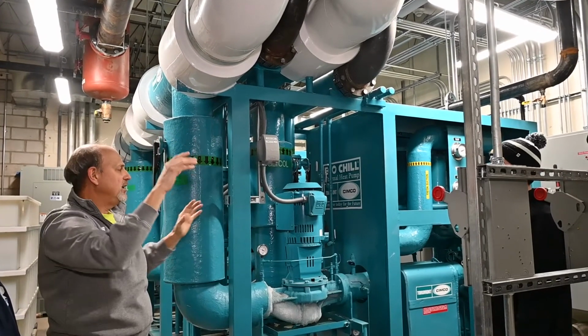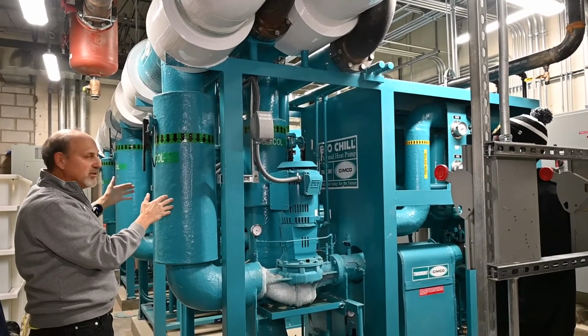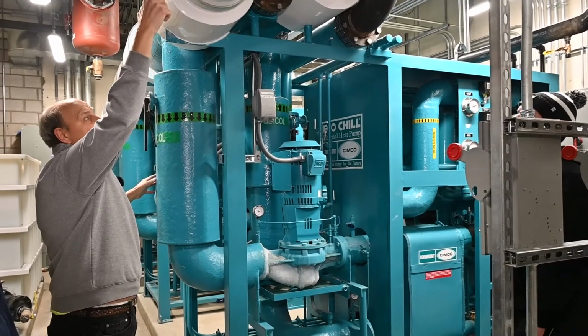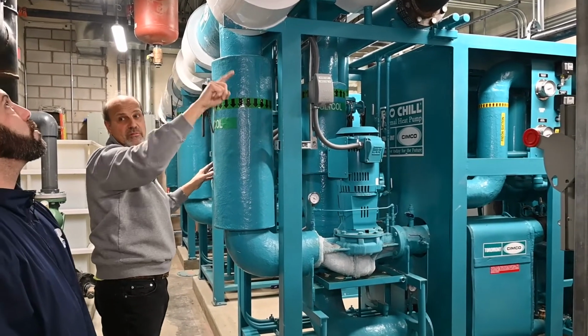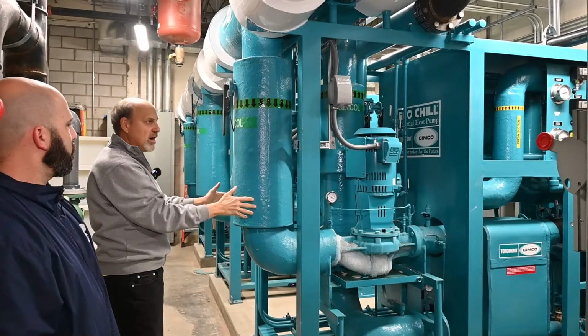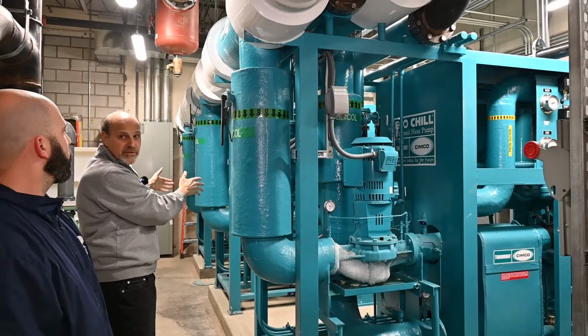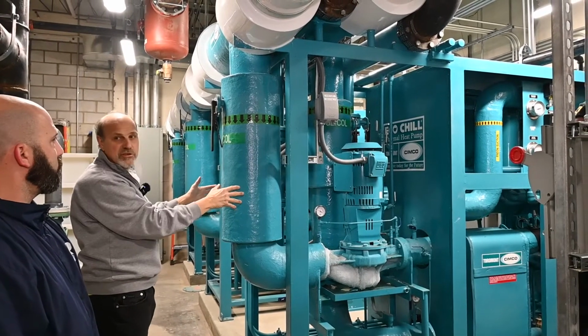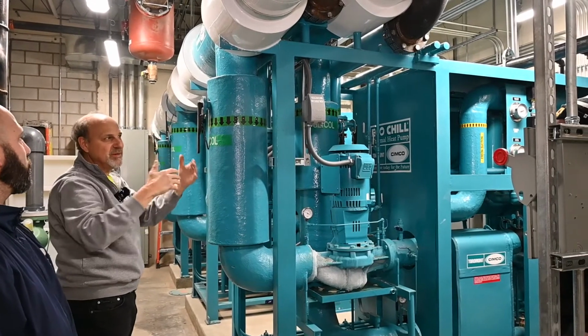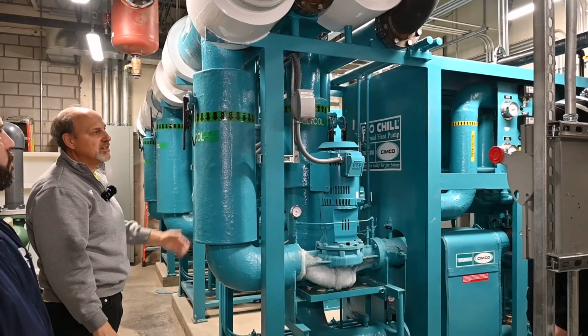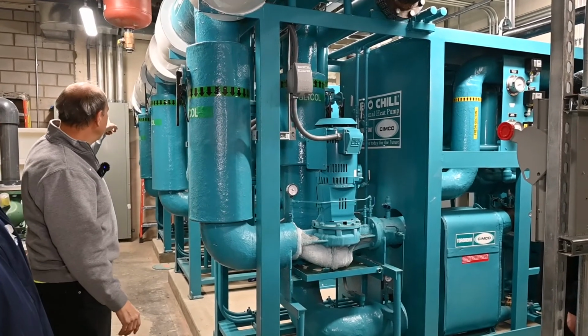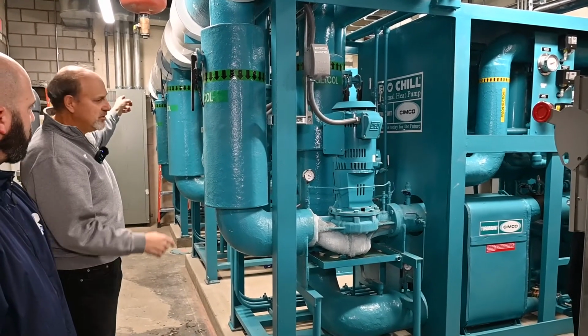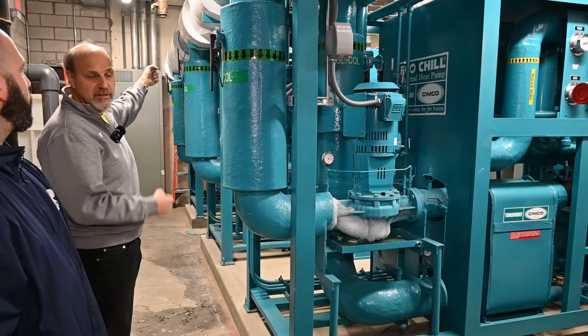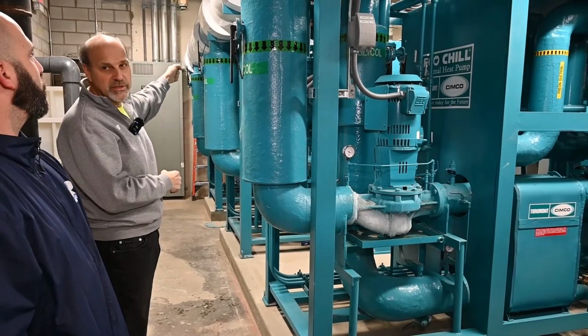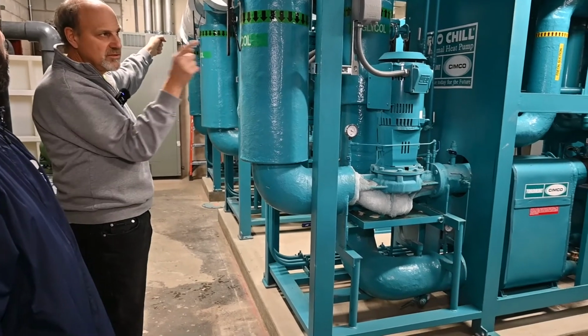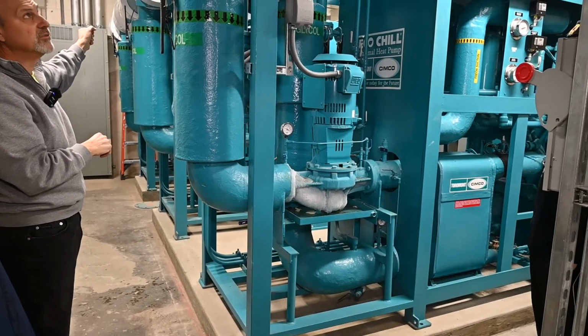at all times. If these chillers start, when one chiller or two chillers, depending on the load, it actually siphons glycol off of this primary or secondary loop, and it goes through a primary loop of one chiller, two chillers, or three chillers. And this is basically injecting cold back into the rink to maintain your ice. That's essentially what this does. So this loop goes back. At the very end, there's a small 2-inch equalizer connection with a ball valve on it. I'll show you that in a minute when we walk down. That's normally closed. And again, it's only used in balancing purposes initially, but that'll always stay closed.